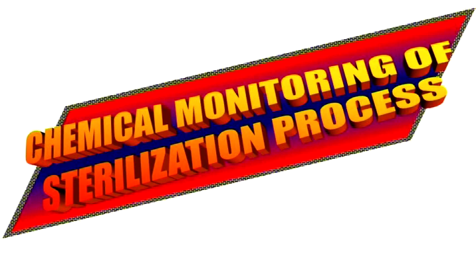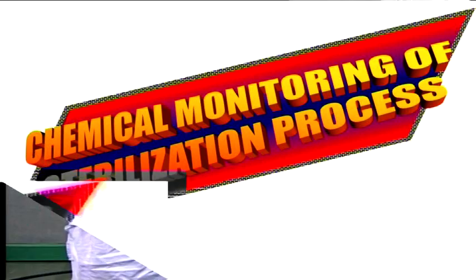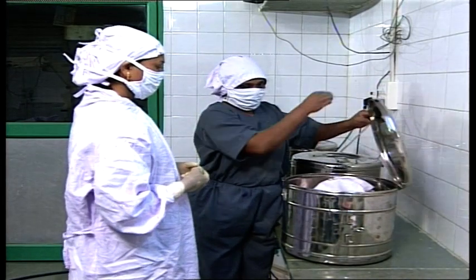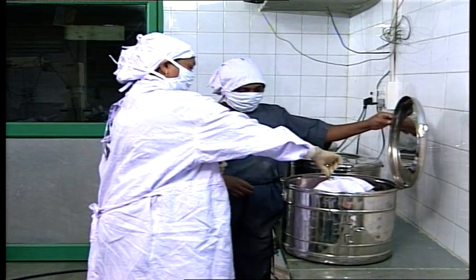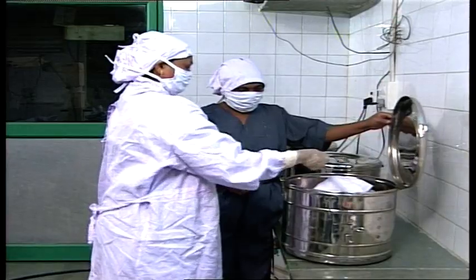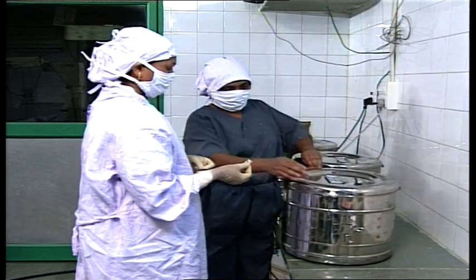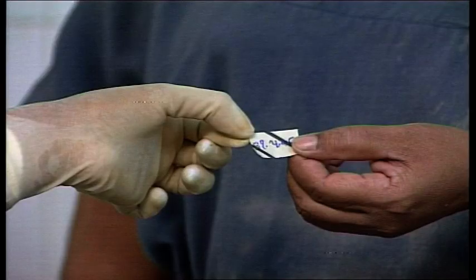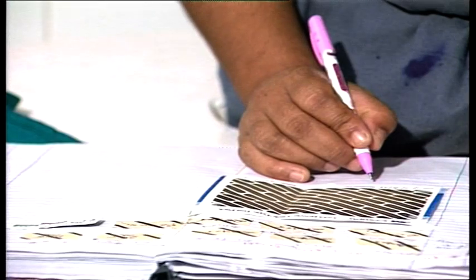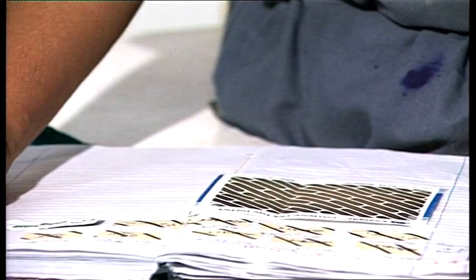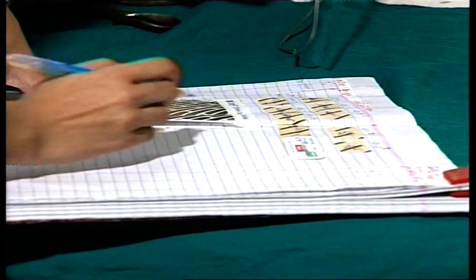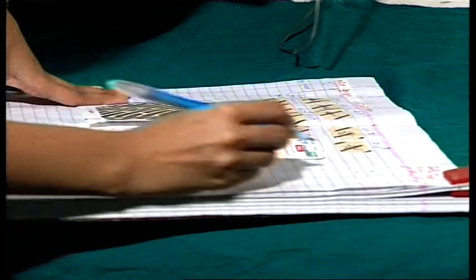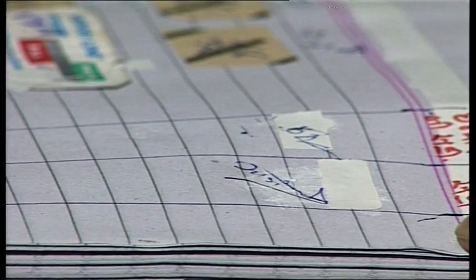Monitoring sterilization process. Chemical monitoring. The autoclave strips should be checked for its color changing to jet black and autoclave strips register should be signed by the theatre in charge and the operating surgeon both after pasting in the register. Once in a week, Bowie Dick test pack or vapor line indicator can be used.